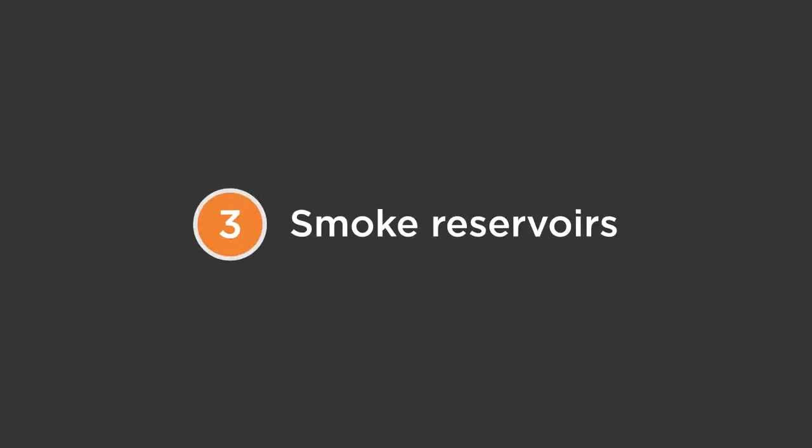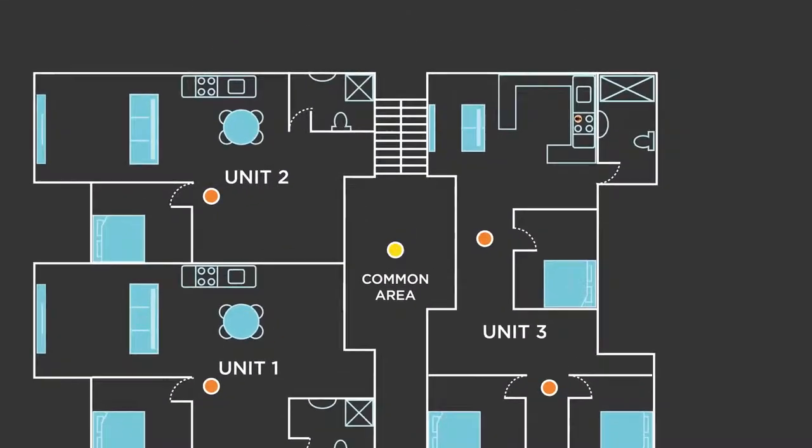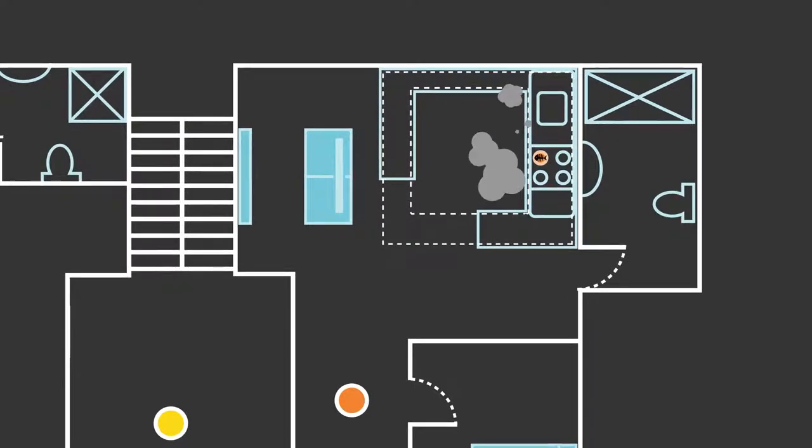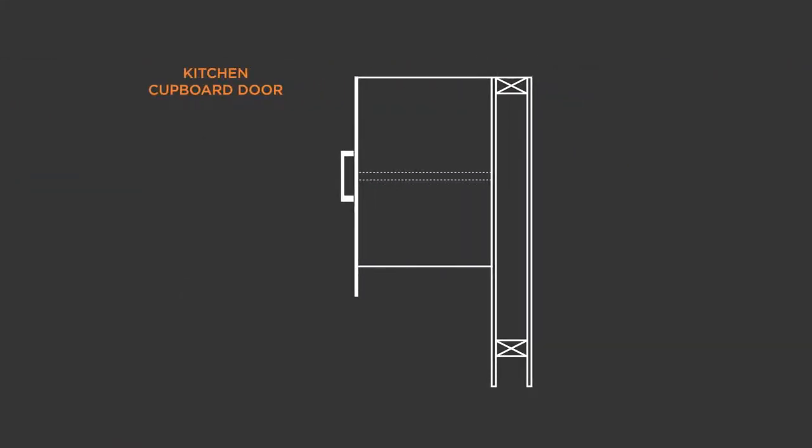Three, smoke reservoirs. Baffles around kitchen areas can act as a reservoir which restricts contaminants from reaching the detector. This can be achieved by installing bulkheads. Likewise, extending the cupboard doors below the base of the cupboard is a simple measure that can assist in delaying activation of the alarm. This curtain system forms a reservoir underneath overhead cupboards and retains cooking vapors and fumes.